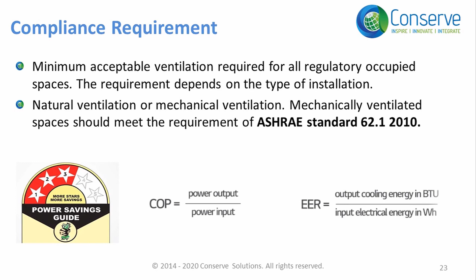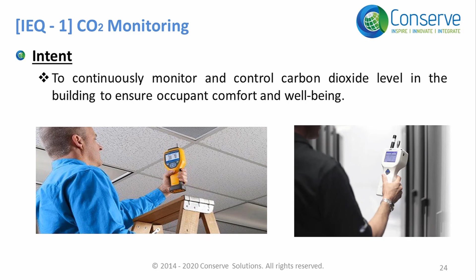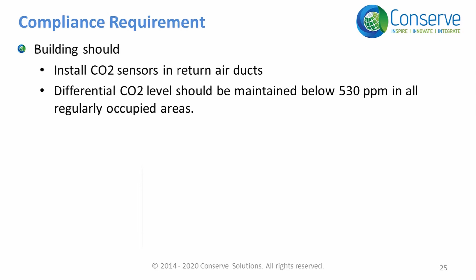Higher concentration of carbon dioxide will cause ill health effects and discomfort to the occupants. Hence, it is necessary to monitor and control the level of CO2 inside the building. The requirement to earn credits is that the project must install CO2 sensors in the return air ducts and maintain a differential CO2 level below 530 ppm in all regularly occupied areas.